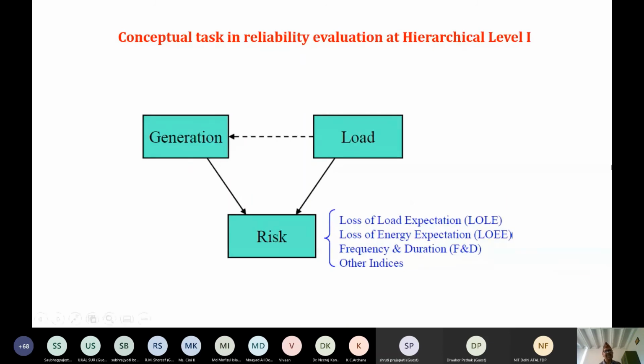In hierarchical level 1 evaluation, what do we do? We have a generation model and a load model, and when we put them together, we obtain the risk model. From this risk model, we get risk parameters, which we call risk indices: loss of load expectation, loss of energy expectation, frequency and duration of load curtailment, and other indices. That's why they are risk indices. And why does load curtailment occur?